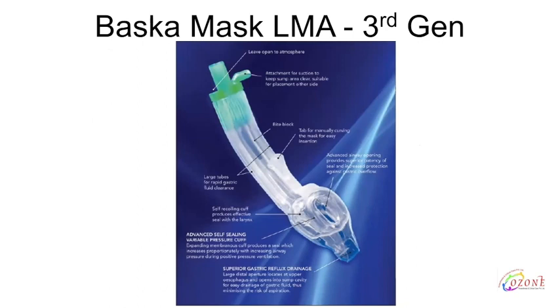It has an attachment for suction. It has a bite block. It has a tab for manually curving the mask for easy insertion. It has large tubes for rapid gastric fluid clearance, and an advanced airway opening, which provides superior patency of seal and increased protection against gastric overflow. It has a self-recoiling cuff, which produces an effective seal with the larynx, and an advanced self-sealing variable pressure cuff. The expanding membranous cuff produces a seal which increases proportionately with increased airway pressure during positive pressure ventilation. It has superior gastric reflux drainage, with a large distal aperture located at the upper esophagus, which opens into the cavity for easy drainage of gastric fluid, and thus minimizes the risk of aspiration.